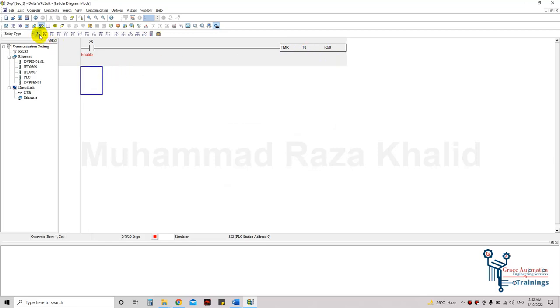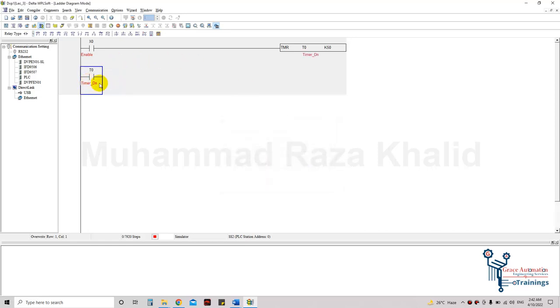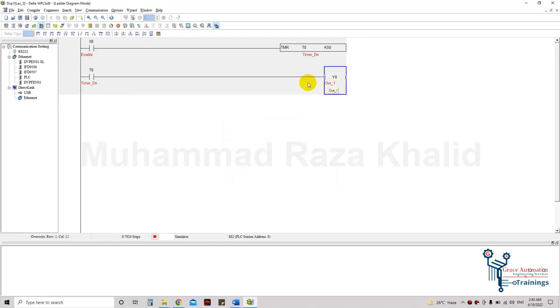Now let's use its normally open contact. I'll change the device name to T with device number 0, and add a comment like 'timer done'. I'll add the output, compile it, and go online — my simulator is already running in the run state. I'll enable it and you can see the timer has started counting, and after 5 seconds the timer done bit is on and the output is on.